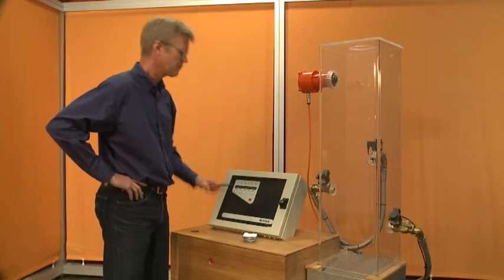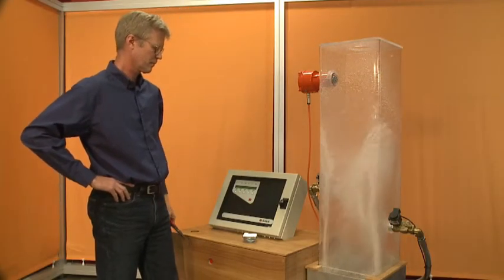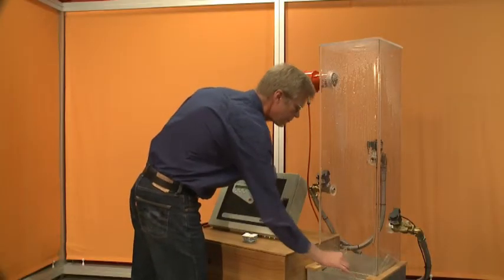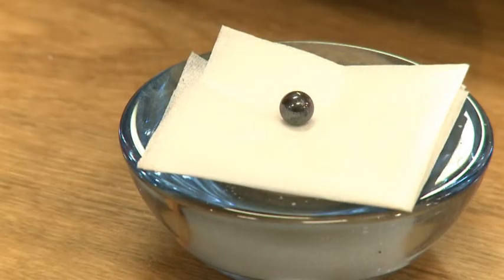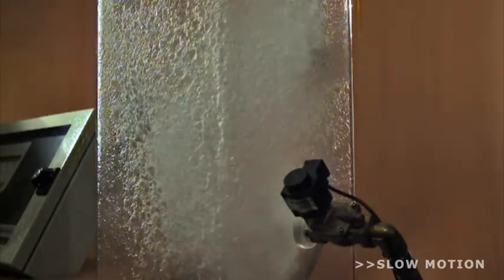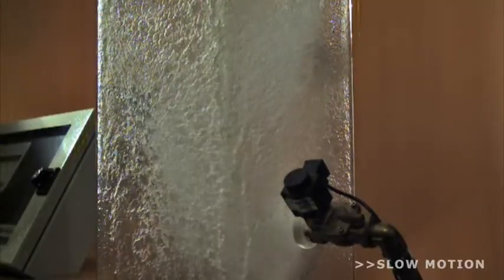As you can see, the system is installed in a plexiglass duct, fully exposed to daylight without causing any false alarms. You can also see that the particle is cooled down so quickly that it can be picked up by hand again. Firefly always uses a minimum of three water nozzles from different directions to penetrate the material flow and ensure coverage of the entire cross-section inside the process duct or chute.